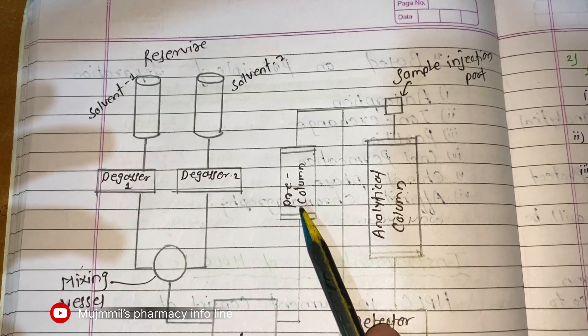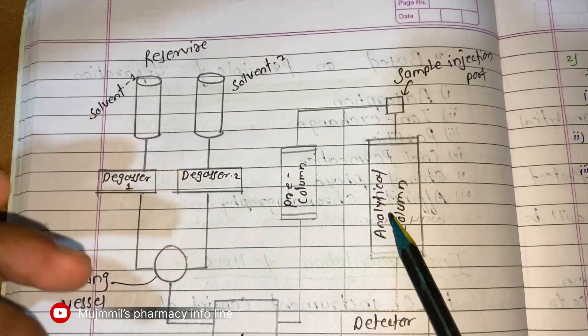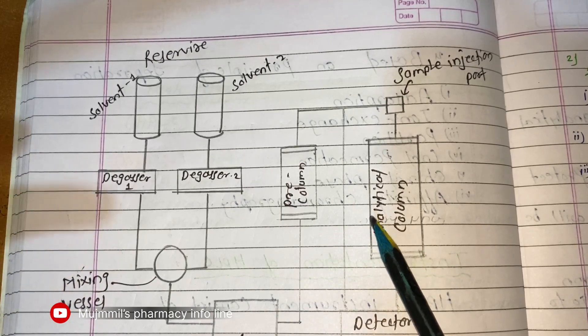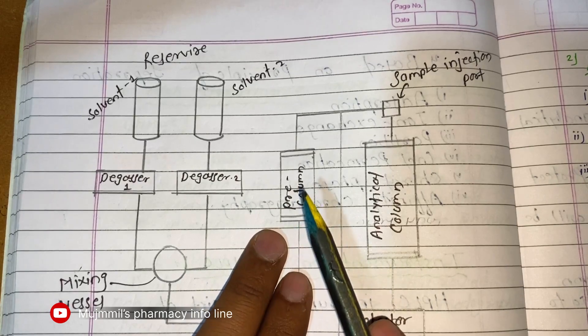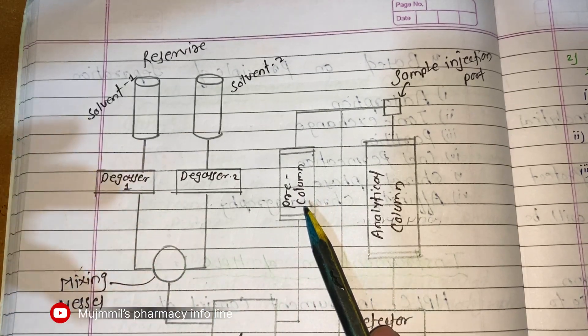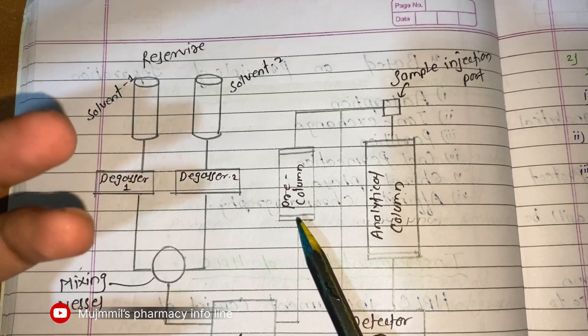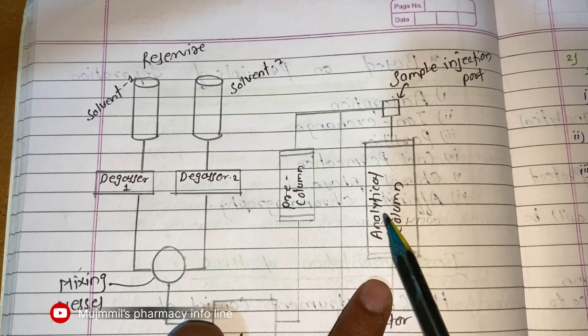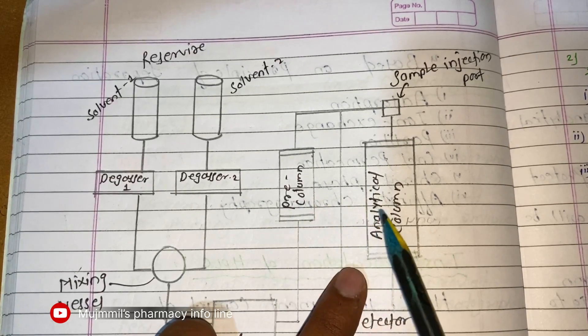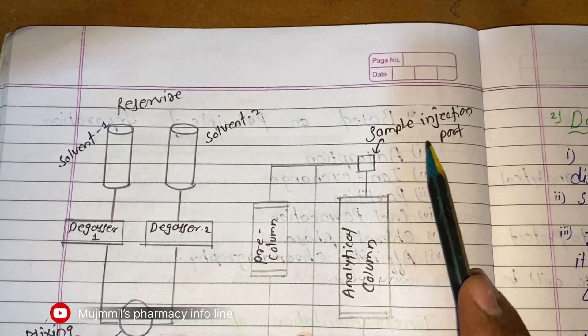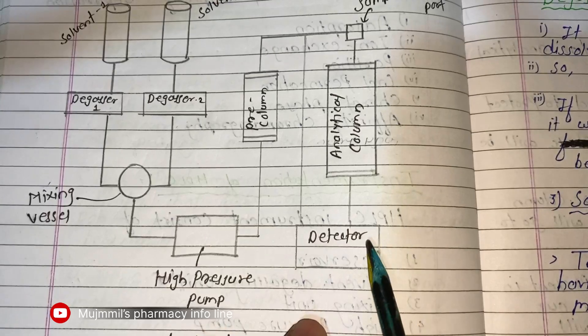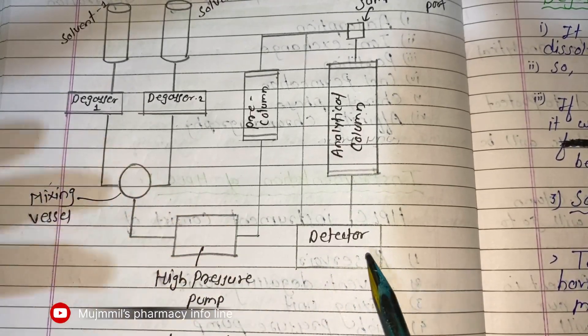The pre-column is also known as a guard column — it protects the analytical column, which is very costly. If any impurity or defect is present in the mobile phase, it will be minimized or detected at the pre-column, so it cannot affect the analytical column. There is a sample inlet port from which we inject our sample into the analytical column; from the analytical column, the sample is detected by the detectors and we get the result.